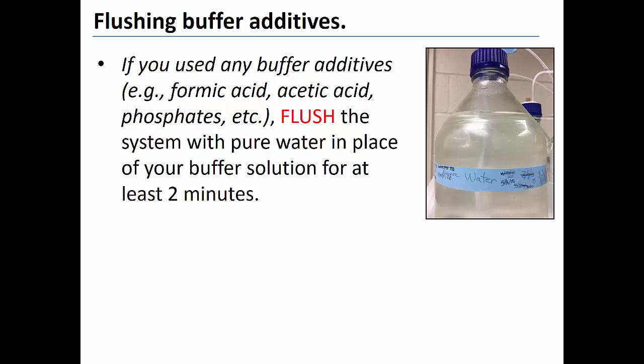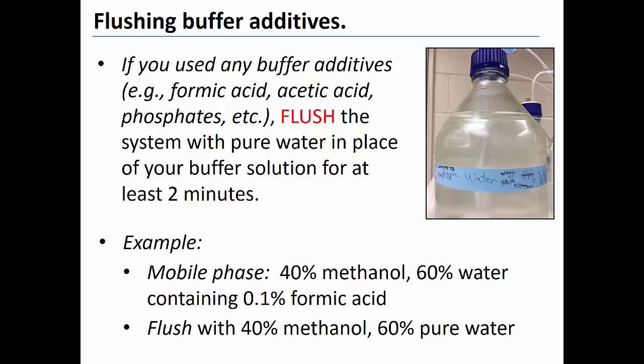For example, if your mobile phase is composed of 40% methanol and 60% water containing 0.1% formic acid, at the end of each batch you must flush the system with 40% methanol and 60% pure water. Doing so removes the buffer additive from the system. This is important because buffer additives can corrode the metallic components of the instrument.